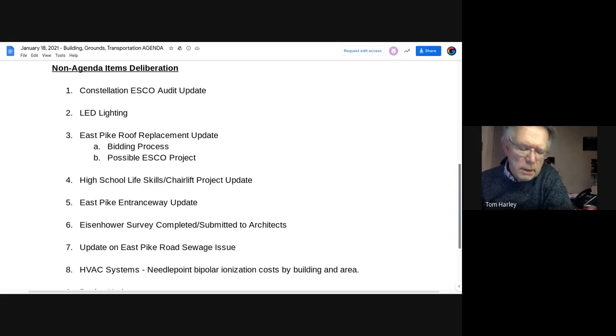My concern is that the ductwork should be inside the insulating envelope, and it was a mistake to put them on the roof in 1990 and 1995. It's a mistake to put them on the roof in 2021. We need to find a way to deal with that duct. You can't run an insulated duct, which is only R5, basically a double pane window, on top of these buildings and expect to have any energy efficiency. So if we're going to put a new machine on, which we probably have to do anyway because of the Freon problem and the life of the machines, we should look at moving the ductwork into the main space, underneath the roof, underneath the insulation, and get it off the roof. So that's my opinion.